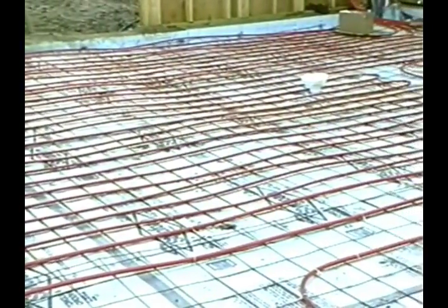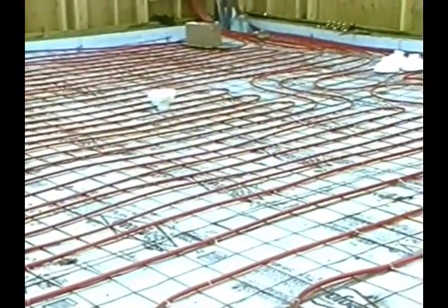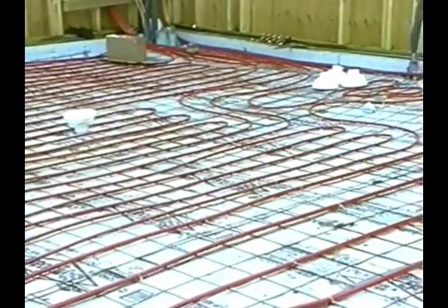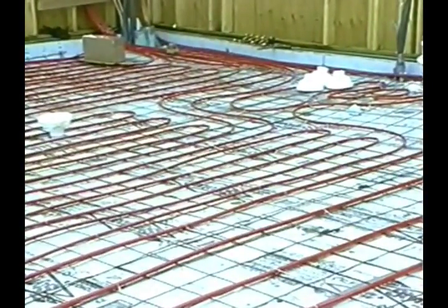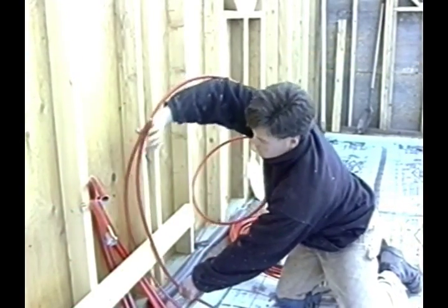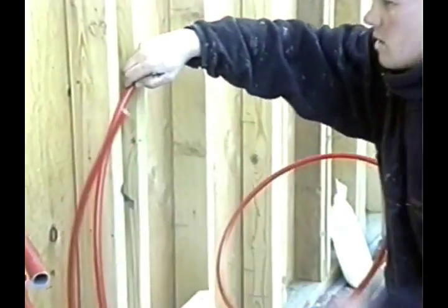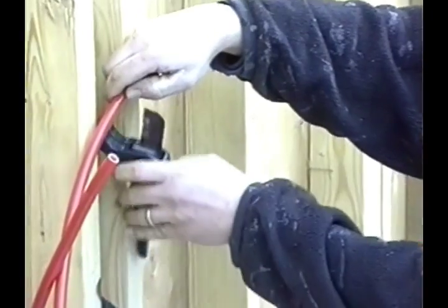The serpentine pattern is used when most heat loss occurs along a wall. The water temperature decreases as it flows through the tube. This layout is used when hotter water needs to be concentrated in areas of high heat loss. The serpentine pattern is the most common method of installation. Once it's been decided which pattern type to use, find the area best suited for your remote manifold. It should be as centrally located as possible and easily accessible.